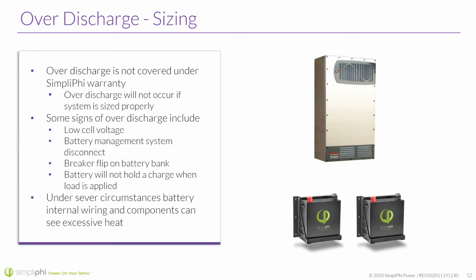Breaker flip on the battery bank. This is really common with over discharge. They are just physical breakers. And if the over discharge event is so significant that it exceeds those limits, the breakers might flip, even if the over discharge has already occurred. And the battery will not hold a charge when load is applied. That's a huge symptom of over discharge.